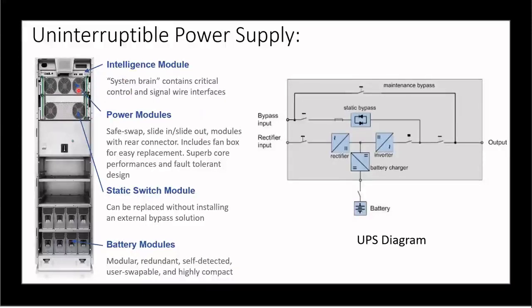What is the advantage of modules is, like this power module, if something is wrong with it, you can just remove it. So when I say you, it is field service technicians who do the service and any maintenance or repair. They just have to remove this module, see what is wrong with it, and fix it. But before, that was not the case. So this helps in maintaining the UPS for a longer time.